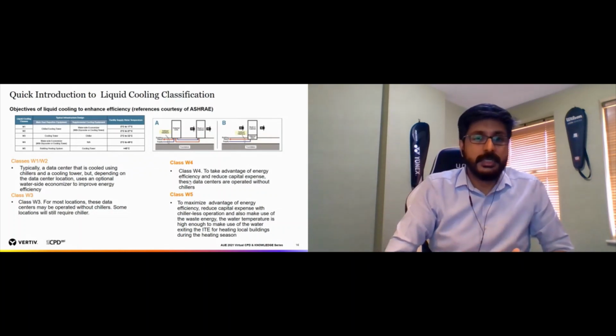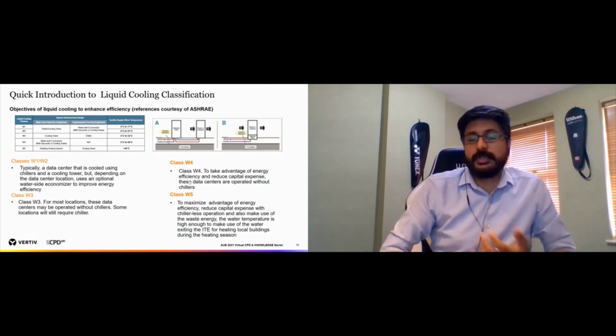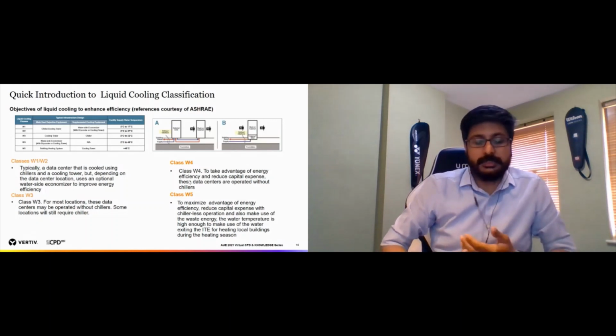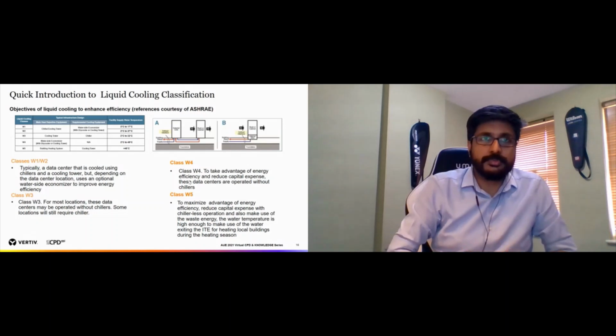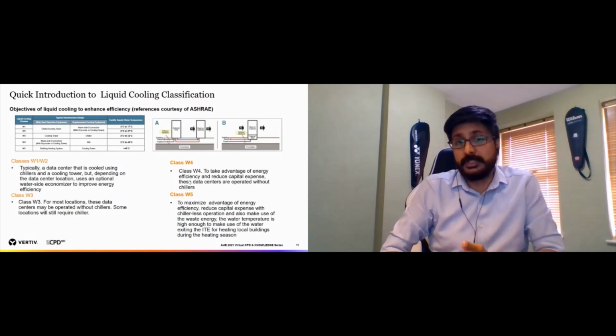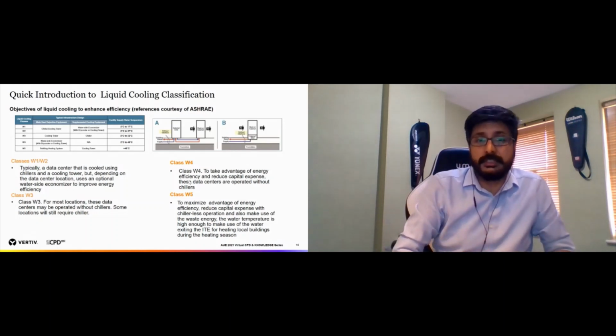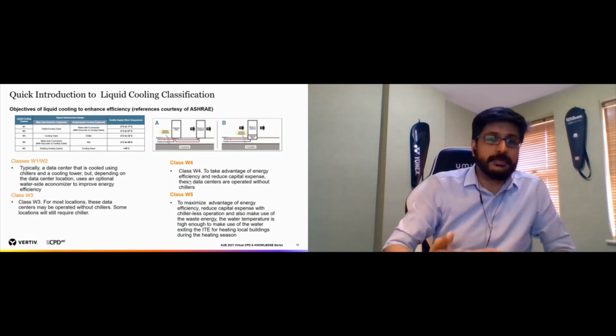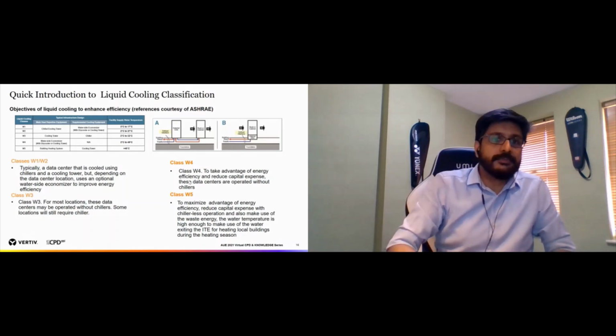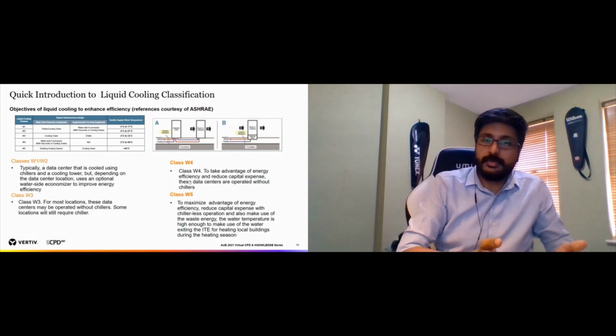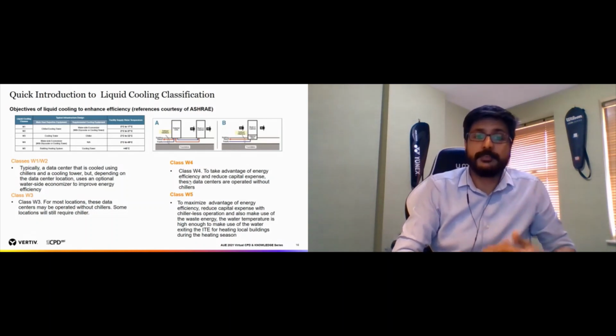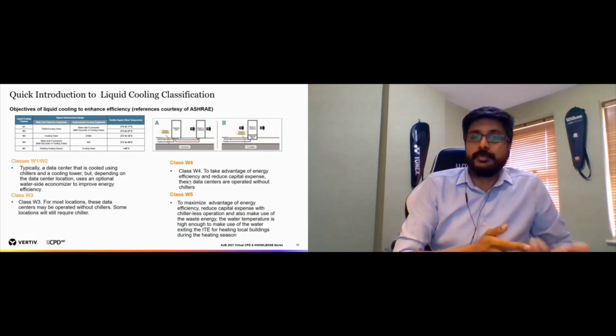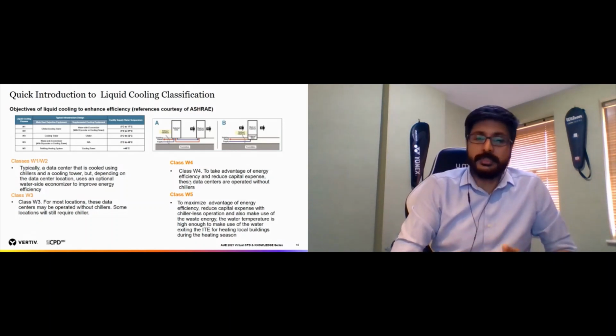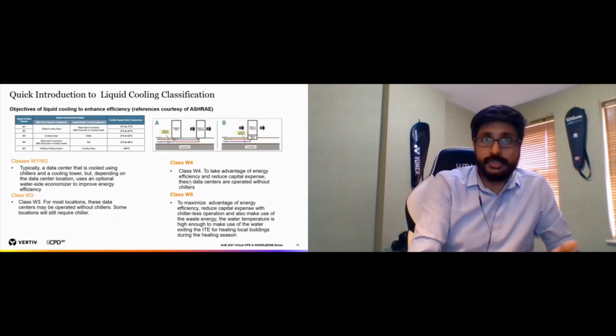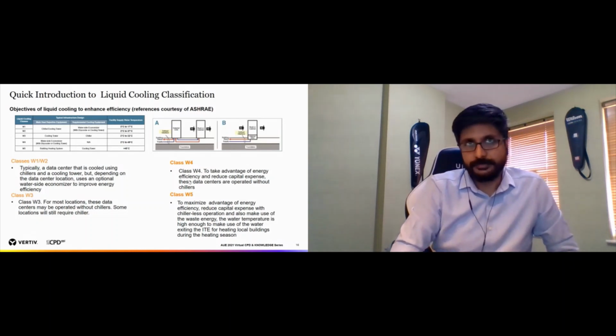into the servers, which means that externally the heat rejection side can be used for heating local buildings as well. So you're basically reusing the heat, and you don't need a chiller or a dry cooler sitting outside. W4 is where the temperature is slightly lower, where instead of a chiller you're now using a dry cooler. It is still efficient as well. But for W1 to W3, you basically use an external chiller, so the water temperature going into the server rooms is quite low.